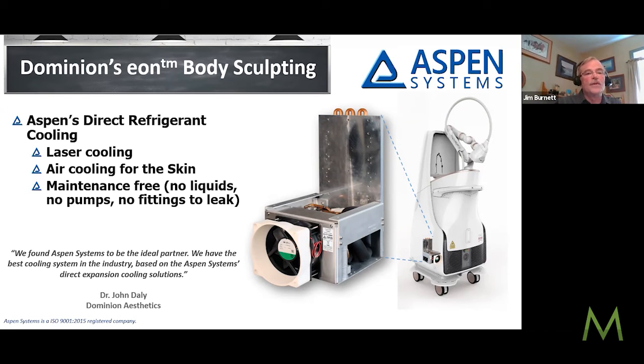The one with the chemo cold cap could not be done with technology that came before us. This system on the screen right now—typically there's no room for a 10-pound compressor in a unit that size, and they have both size and weight limits. So having two separate systems inside a unit that size was impossible before we came along, and before the willingness to integrate a direct refrigerant. If this were a chiller, it would be twice the size and have three times the maintenance, because the compressor will last 100,000 hours, while the best pump lasts maybe 30 or 40,000 hours.